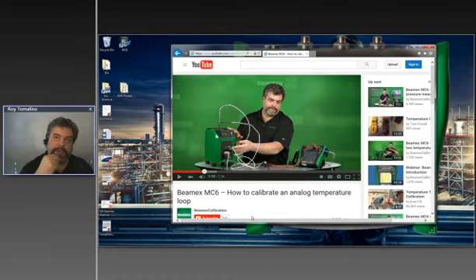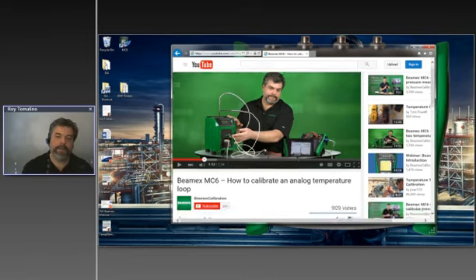Now, if there is error, we can trim it on the transmitter itself, or, to the question that was asked previously, on the control system, you could enter an offset in your control system to remove any offset that's inside the probe or the transmitter. So that would work as well.